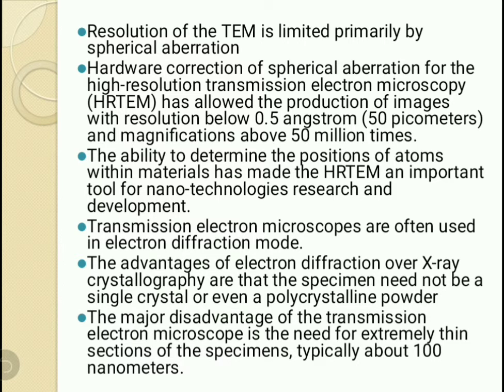The resolution of TEM is limited primarily by spherical aberration. Then hardware correction of spherical aberration for the high resolution transmission electron microscope has allowed production of images with a resolution of 0.5 angstrom and magnification above 50 million times. So these are the advantages.